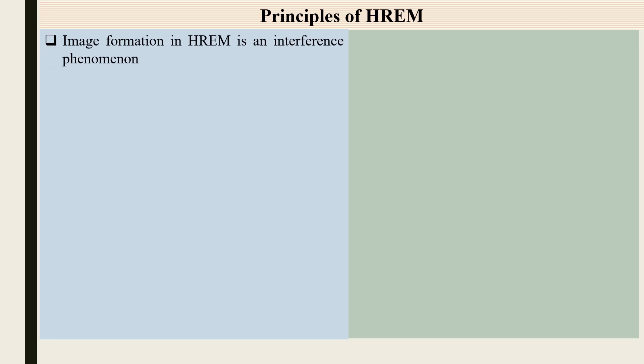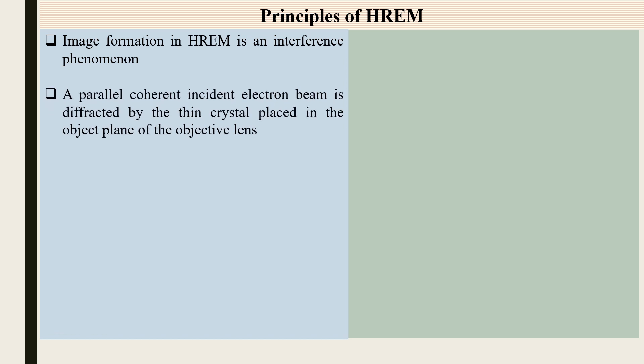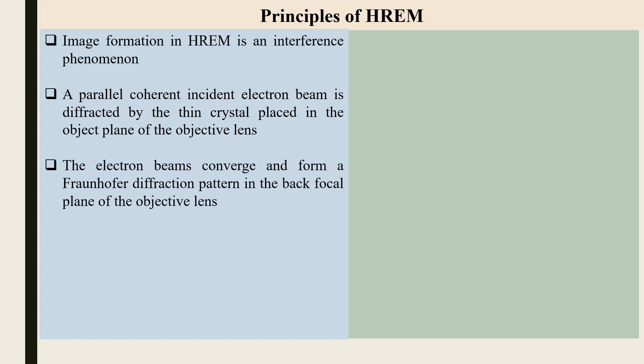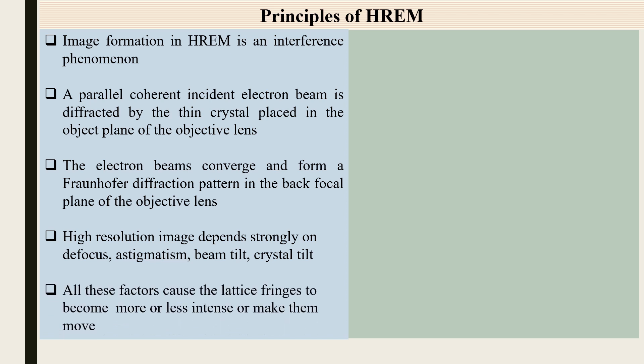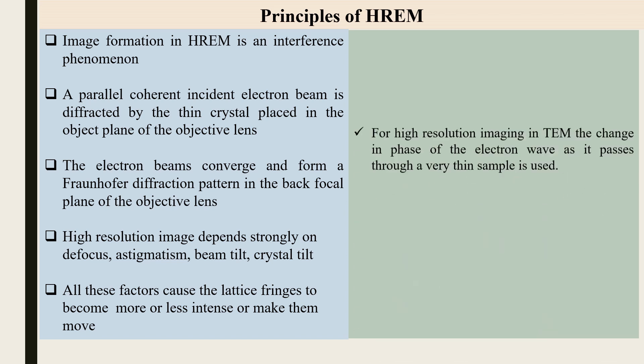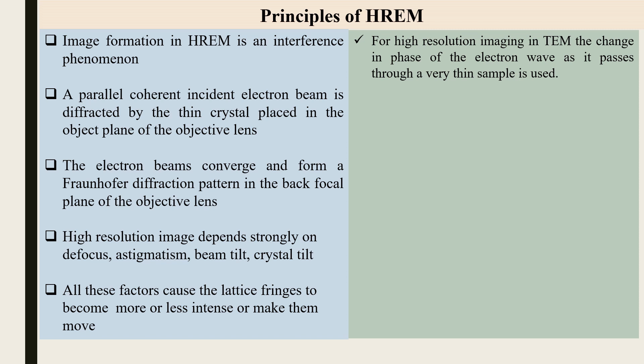For high resolution electron microscopy, the image formation is an interference phenomenon. A parallel coherent incident electron beam is diffracted by a thin crystal placed in the object plane of the objective lens. The electron beams converge and form a Fraunhofer diffraction pattern in the back focal plane of the objective lens. The high resolution image depends strongly on defocus, astigmatism, beam tilt, and crystal tilt — all these factors cause lattice fringes to become more or less intense or to move.